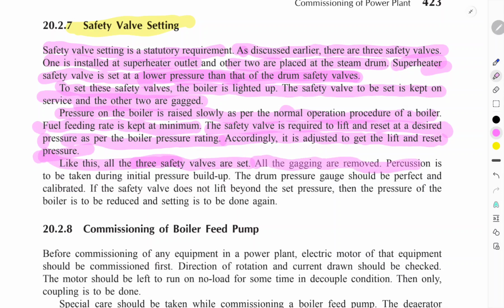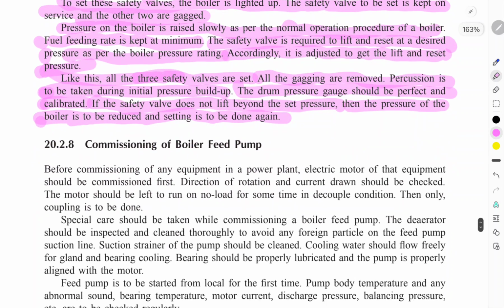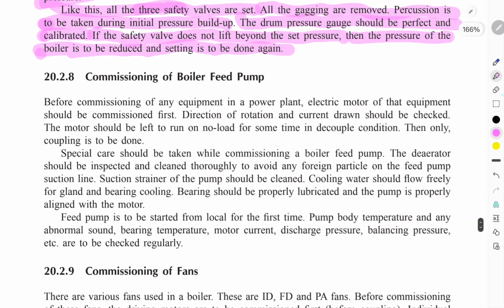All gagging removal procedures have to be followed during the initial pressure build-up. The drum pressure gauge should be perfect and calibrated. If the safety valve does not lift at the set pressure, then the pressure of the boiler is to be reduced and the setting is to be done again. Commissioning of the feed water pump.